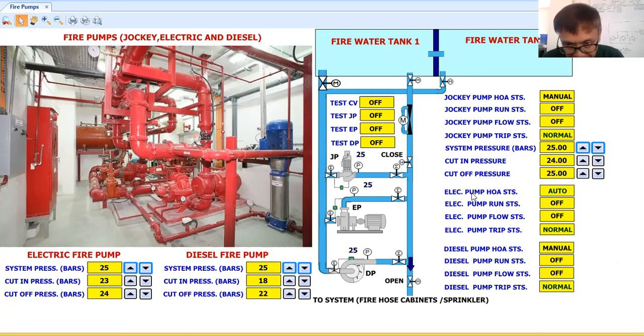In testing these fire pumps, first they will test the jockey pump. As I said, this jockey pump has its own motor control. Inside the motor control, there will be a pressure switch. So the mechanical engineer, the one responsible for testing and commissioning this, should be capable of adjusting the pressure switch. With the pressure switch, you will adjust the cut-in and cut-off pressure.